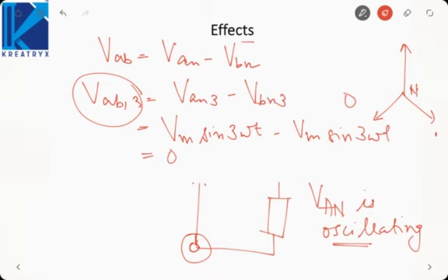So if we are connecting a three phase load, then the voltage across that load will be line voltage, which does not contain any third harmonic. So we can connect any three phase load, that is not an issue. But the thing is, third harmonic voltages are present at the neutral point, due to which neutral is oscillating or floating. So if we connect a single phase load, then the phase voltage will appear across the load which contains the third harmonic. So the amplitude of the voltage will not be fixed. Okay, the amplitude will be variable, due to which we will have some fluctuation in the load which is undesirable.